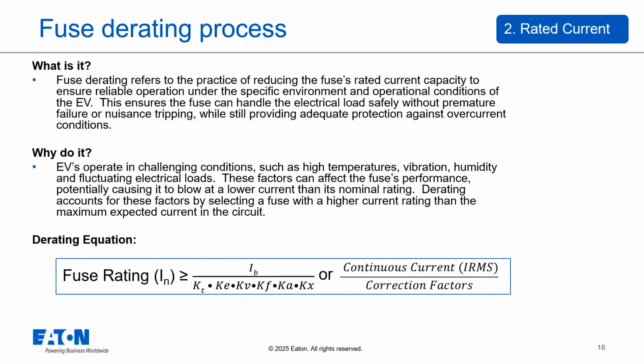The core concept is captured in the derating equation. You calculate a minimum required fuse rating, IN, based on the continuous current divided by a correction factor. The correction factor is a product of several individual derating factors that account for specific environmental conditions. These correction factors reduce the fuse's rated current capacity to account for the harsh automotive environment compared to standard industrial uses. Here are the main factors.